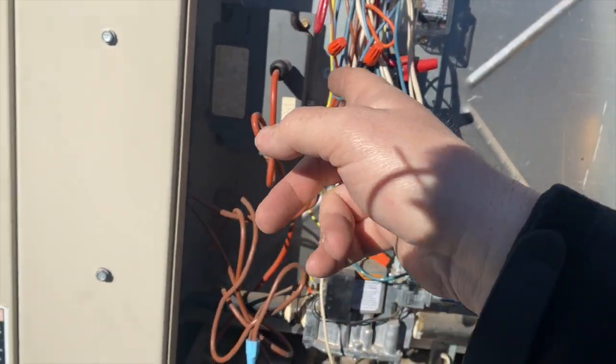This goes to the motor and then these go to that centrifugal switch. If this isn't closing then that's why our igniter is not coming on. If that's the case we shouldn't be getting any voltage to the module. If it's not closing, if it is closing then we should have voltage. If we have no voltage then it's probably the switch. If we do have voltage then it's probably the module.